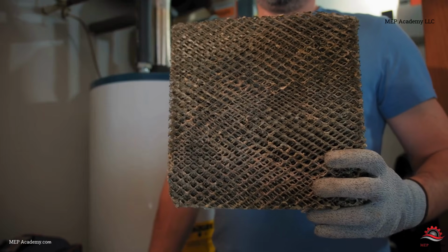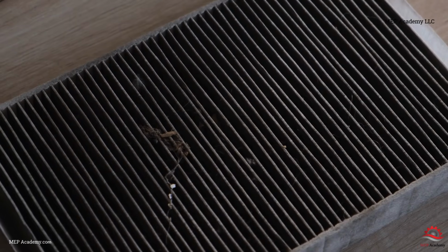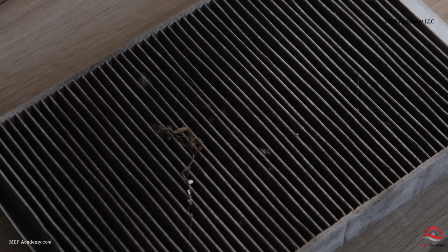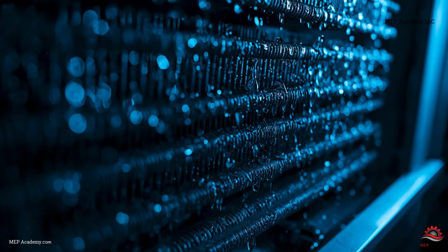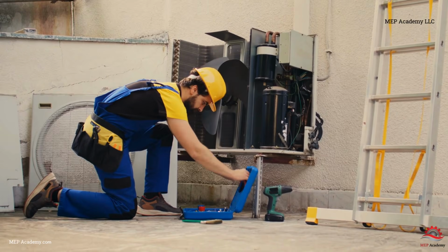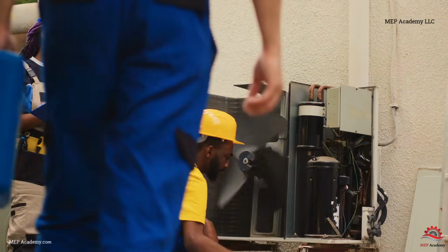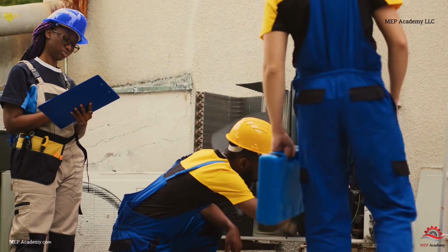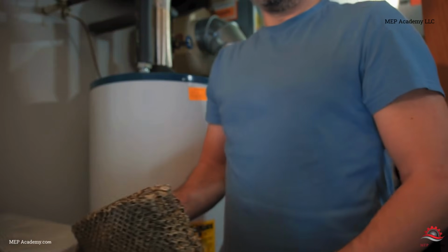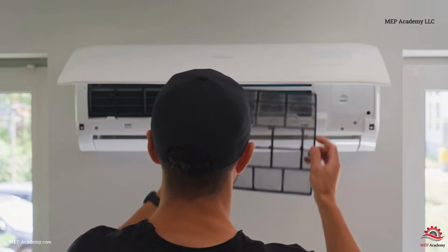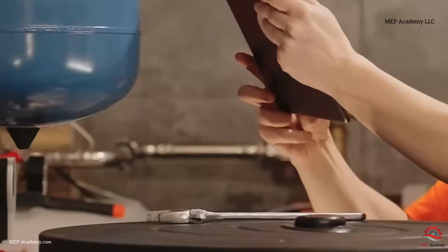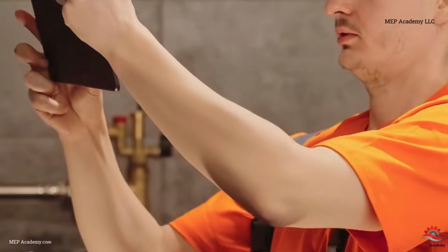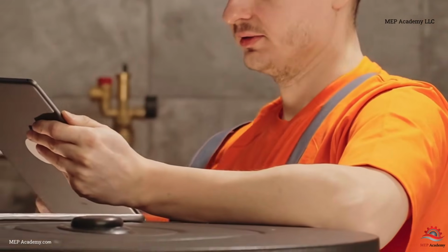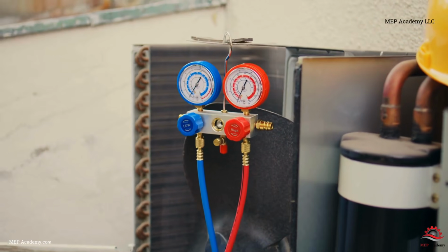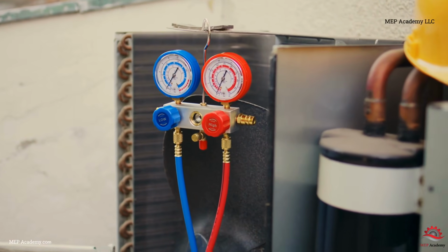The most common causes are dirty air filters, plugged evaporator coils, failed blower motors, slipping fan belts, collapsed ductwork, or closed dampers. Low refrigerant charge can also cause coil temperatures to fall below freezing. The solution begins with restoring proper airflow. Check filters, inspect coils, verify fan operation, measure static pressure. Only after airflow is confirmed should refrigerant levels be evaluated. Many systems receive unnecessary refrigerant because the actual problem was airflow all along.